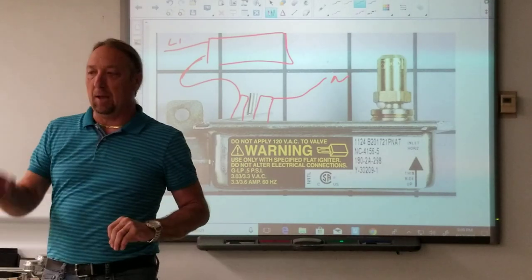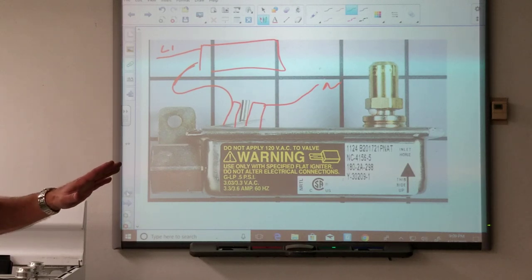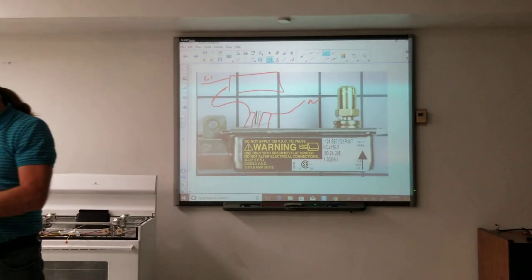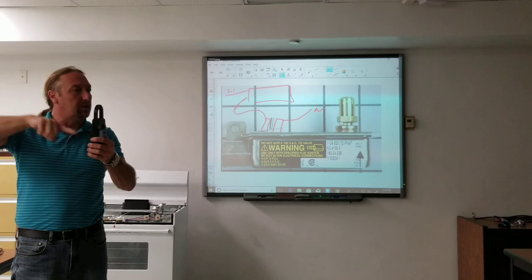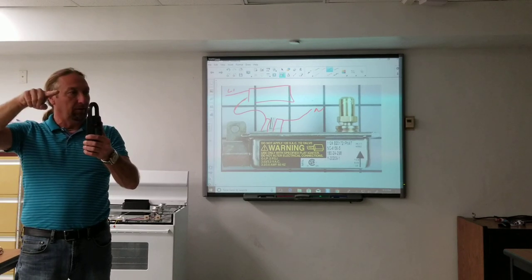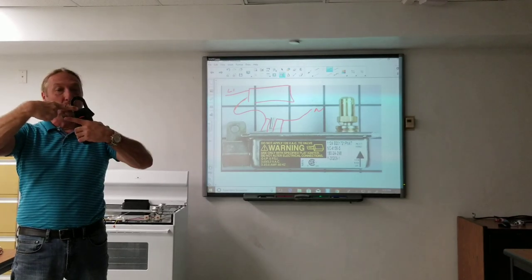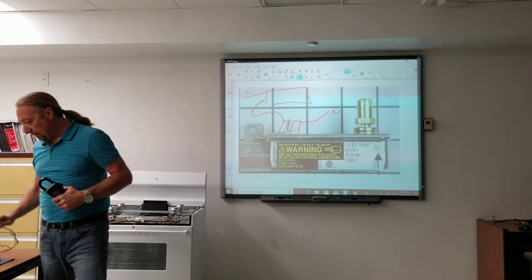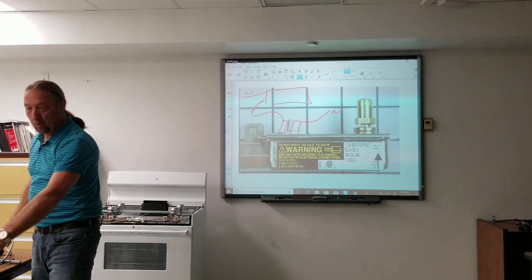When we check amperage we clamp around only one wire. If you clamp around two wires or more you're not going to get a reading. What happens is electricity flows through one wire one way, flows through another wire the other way. When we check amperage around the wire like this, what it's measuring is as electricity flows through the wire it creates a magnetic field in the air. The more electricity, the bigger the magnet. But if you put two wires going the opposite way, the two magnetic fields cancel each other out. The meter can't read it. So you can't go across a power cord like this and measure amperage. You have to go down where the wires in the oven break up to a single wire.